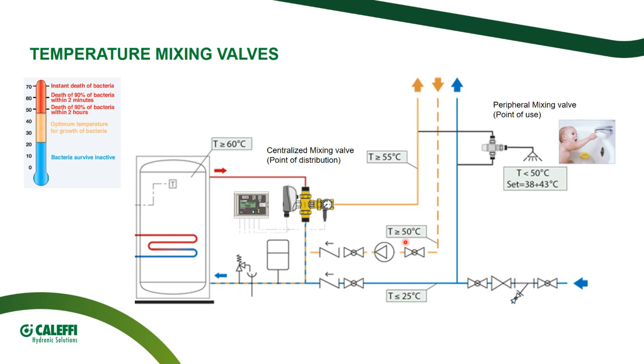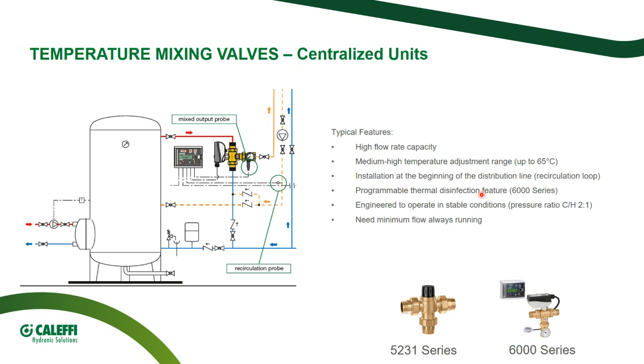It's a typical value. Before the final use, in order to protect the users, that can be also weak people or very delicate, like children, elder people, or if you imagine people in the hospital, you have to ensure a final temperature reduction up to 38, 40, or 43 Celsius degrees. And this will be obtained with a peripheral mixing valve installed at the point of use. Let's start from the first valve.